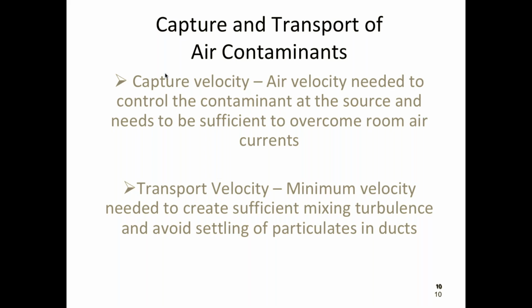Transport velocity. Now that you suck this stuff into the ductwork, you've got to get it through the ductwork, out of the building, and somewhere where it's safe, right? You might have to filter it out and so on. You need to have enough velocity of air moving through the ductwork so that the stuff doesn't drop out and clog up the equipment and eventually wind up clogging up your ductwork and stuff like that. Yes?